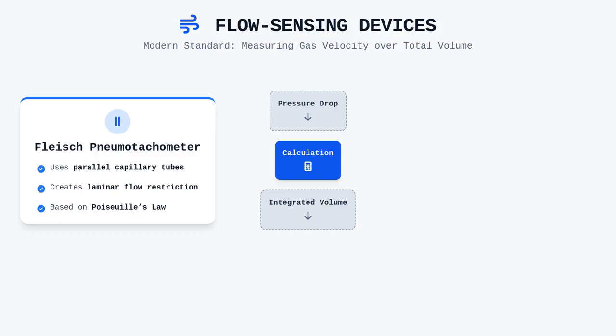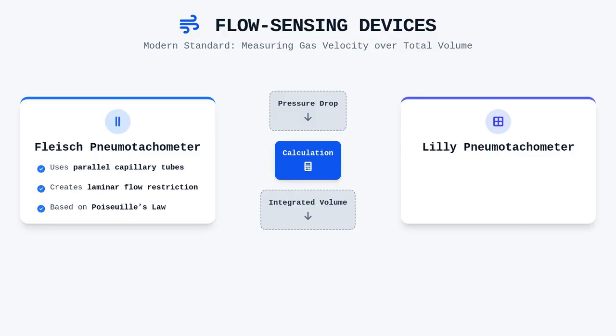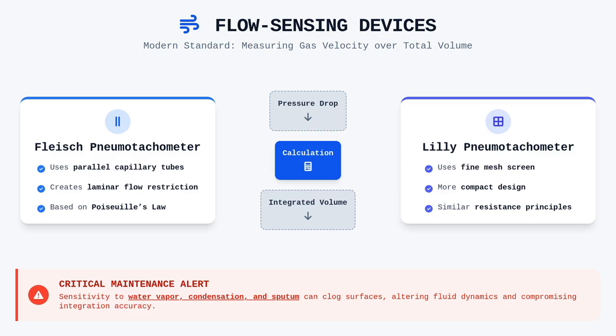A Lilly pneumotachometer functions similarly but uses a fine mesh screen to create the resistance, which is often more compact than the capillary bundles found in Fleisch devices. Both systems suffer from sensitivity to water vapor and condensation, which can clog the screen or capillaries and significantly skew resistance calculations. Proper maintenance of these mesh surfaces is critical, as any accumulation of sputum or moisture changes the fluid dynamics and immediately compromises the accuracy of the integration.